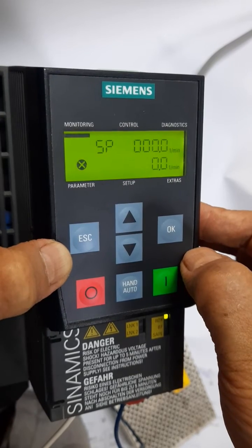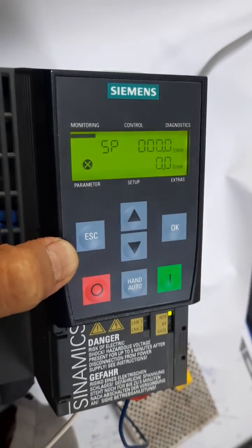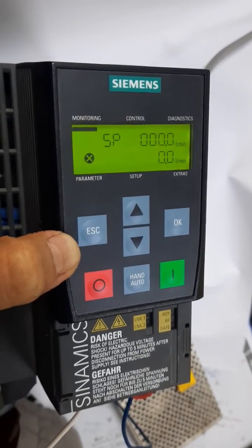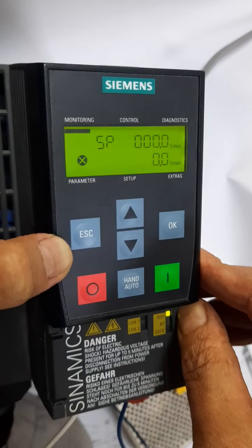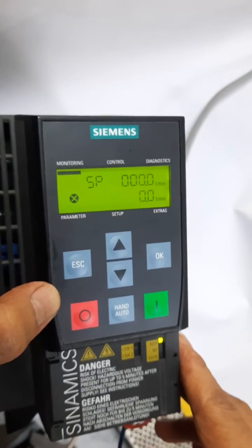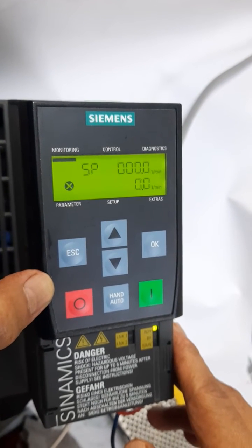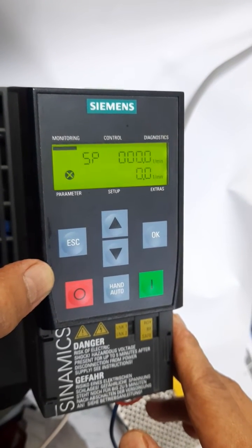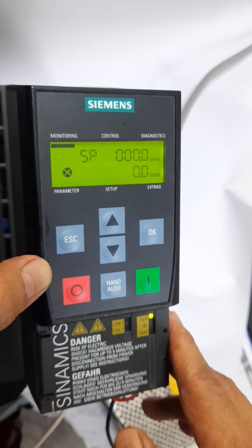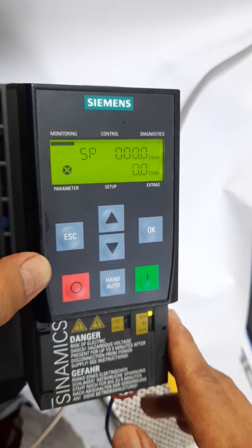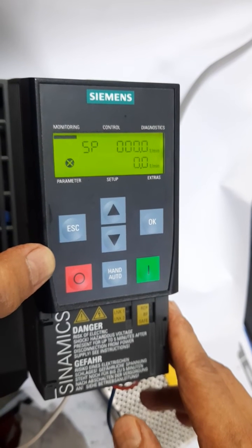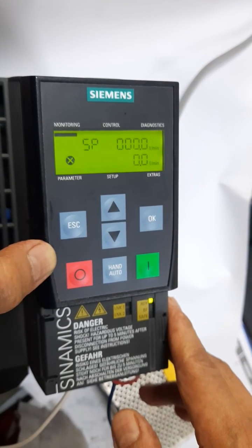Without passing any extra time — as we have seen, it takes so much time to go to a parameter by pressing the up and down arrow keys. But if you follow this way, you will get to your desired parameter very quickly. And if you want to change the ramp down time, the same way you have to go to parameter number P1121, and there you will get your ramp down time and change it according to your requirement.